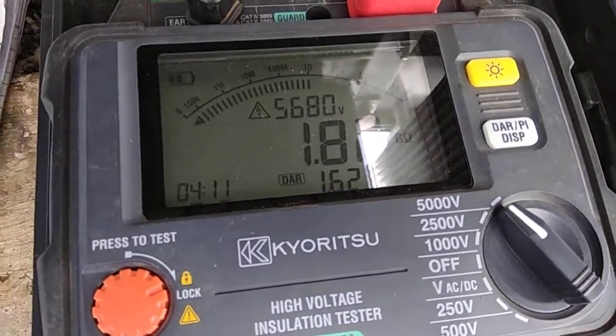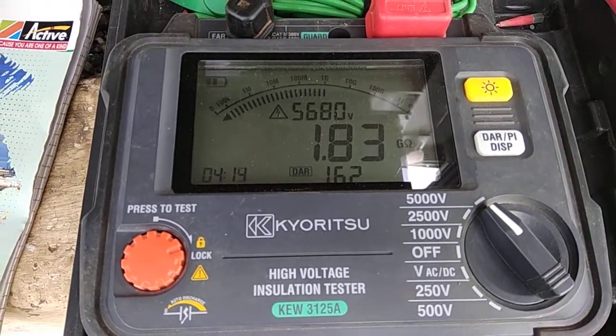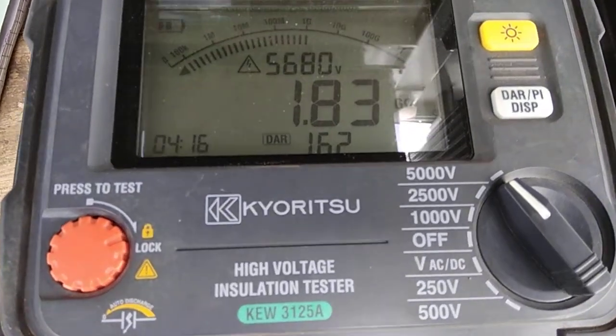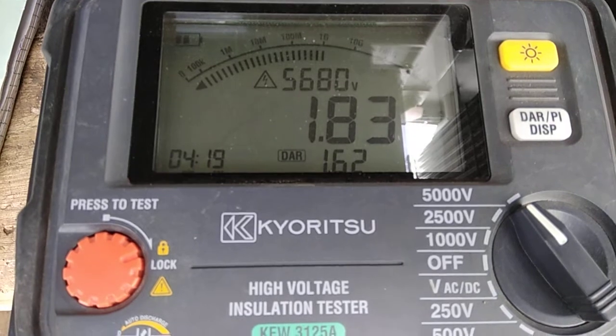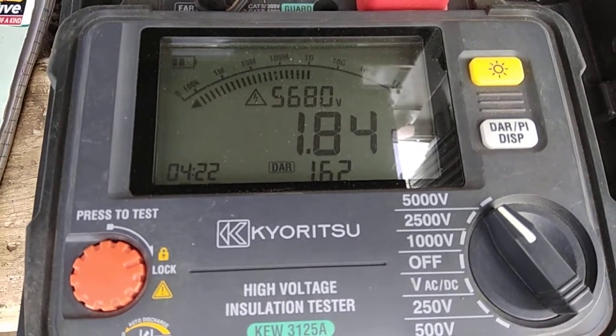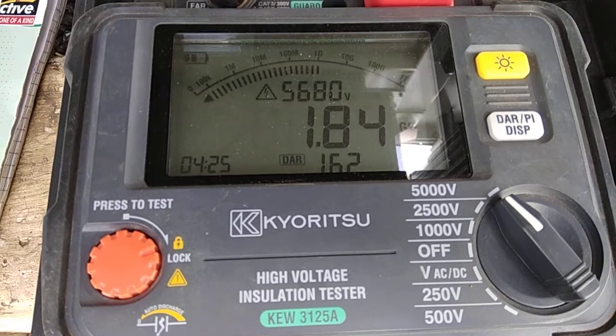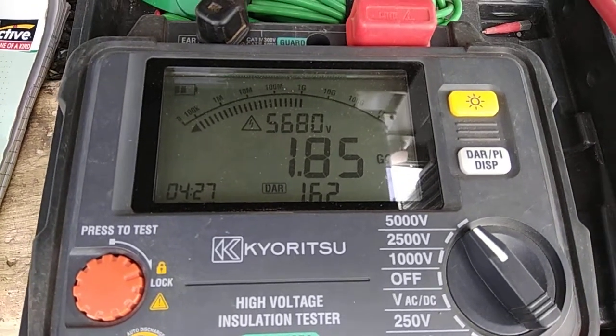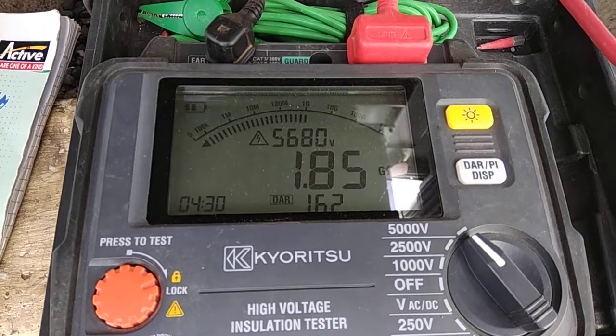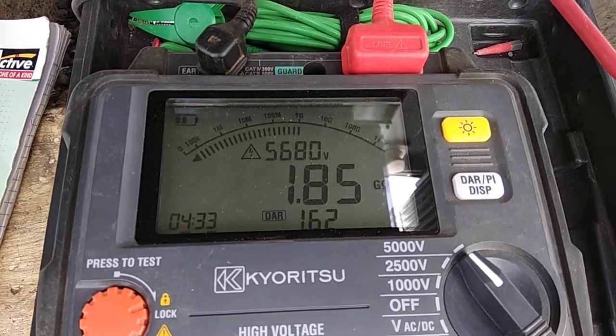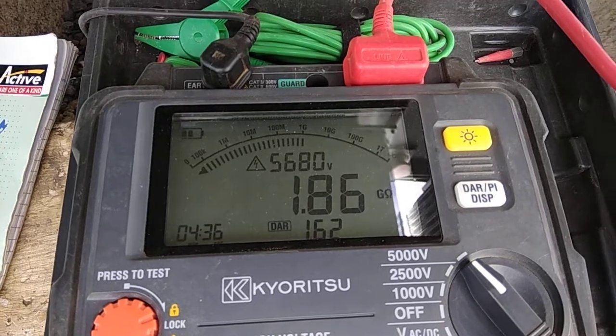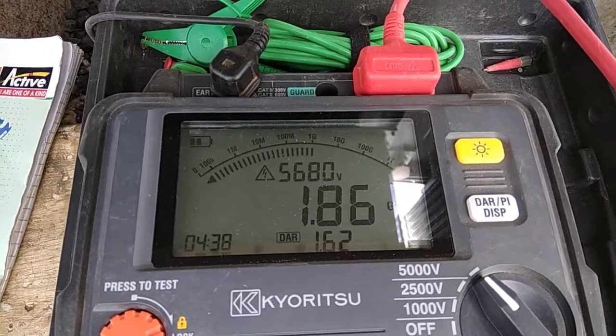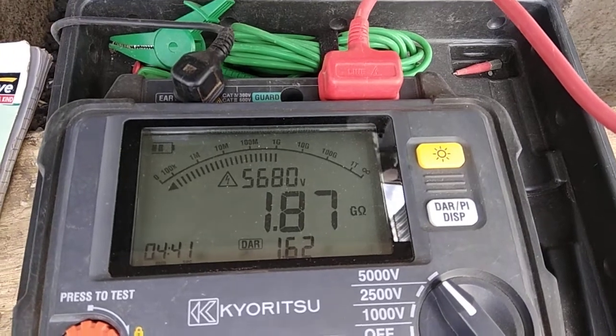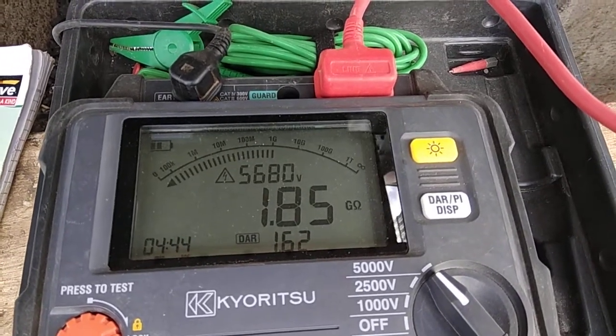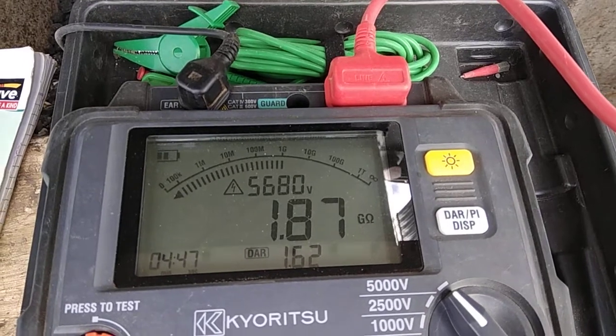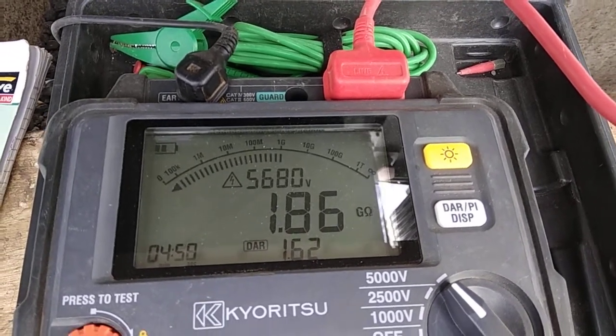And if you see carefully, the test is going on and we are performing the PI of the transformer, and DAR is already calculated, that is 1.62. It is calculated in 1 minute, but after 10 minutes we will be able to see the PI value. The PI value is preferred above 2. If the PI value is above 2, then the situation is very good, but we consider 1.5 considering the environmental situations. For DAR, values above 1 are acceptable, but if our value is above 1.4, then this is considered excellent condition of the insulation.